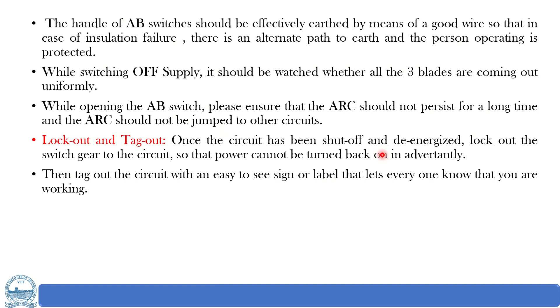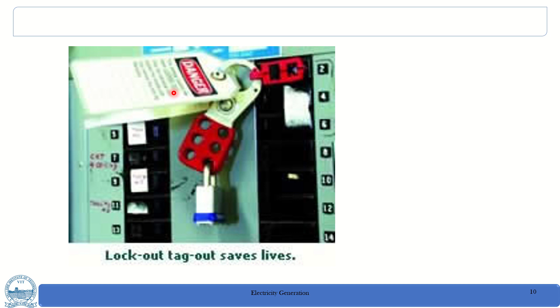That is, unknowingly, no one can switch it on, and you have to mark a tag that this should not be operated and someone is working on the line. So the tag is for the indication, and this lock is for keeping the breaker in the de-energized position. This is one sample of it. After opening, it is being locked. The lever is locked and a tag is attached, not to switch on, indicating some work is going on.